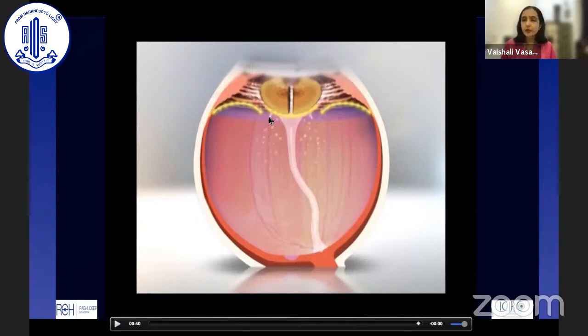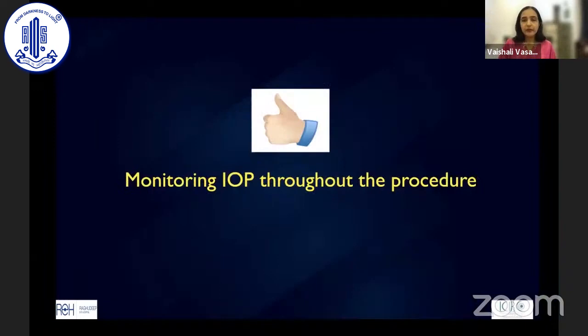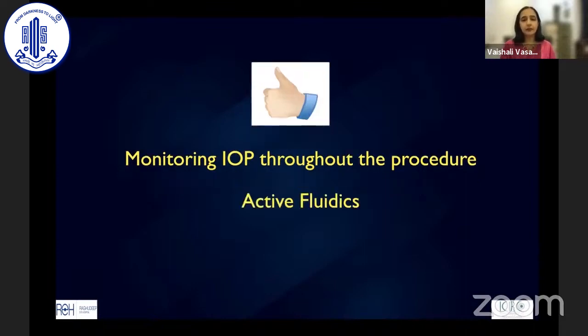As phaco was performed, as soon as we went to foot pedal position one, the whole vitreous face was pushed back, and at position zero it came forward — significant trampolining. When bottle height and flow rate were raised to 40 cc/min, the amplitude of fluctuations increased dramatically, and echoes appeared in the vitreous cavity even with an intact posterior capsule. This led us to understand that the anterior vitreous face can rupture purely from elevated anterior chamber pressure — without any mechanical trauma. This is critical, as inflammatory mediators and infectious agents can then pass from anterior to posterior segment. We need to monitor and, if possible, actively control this pressure.